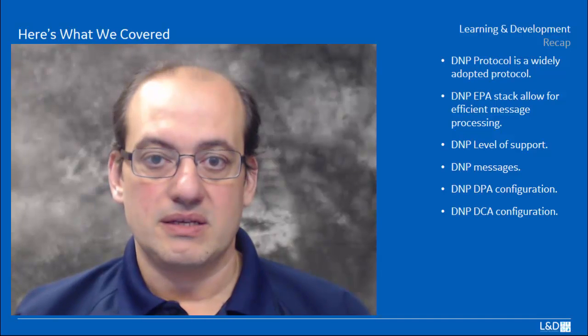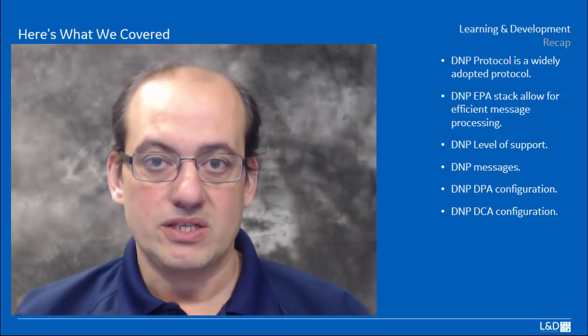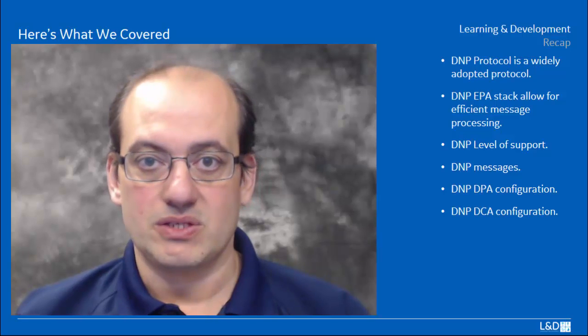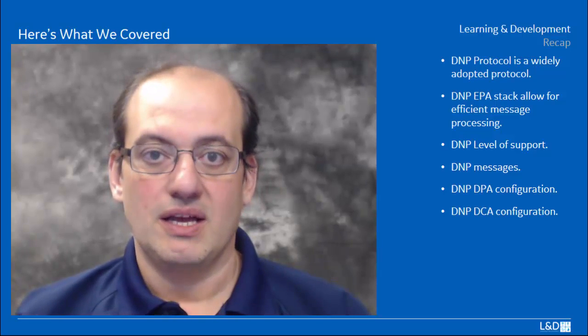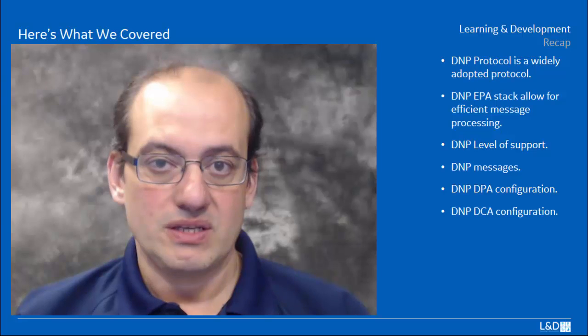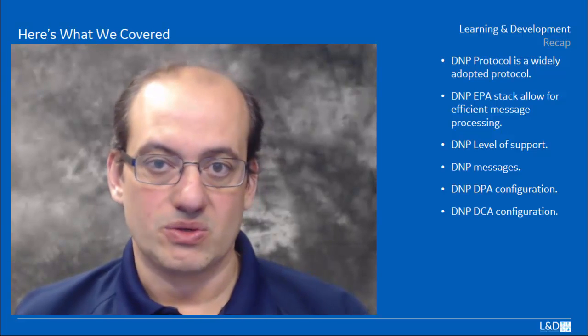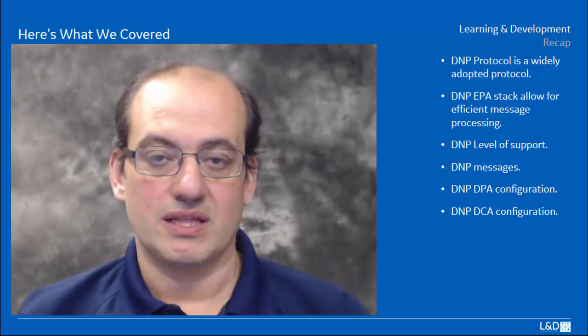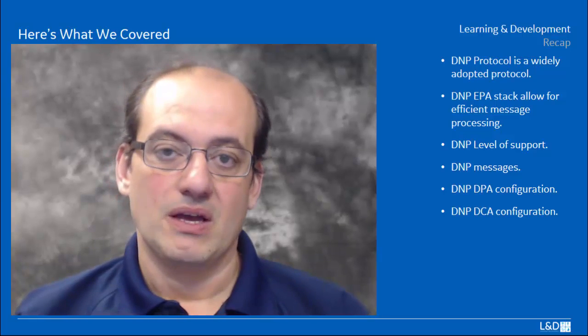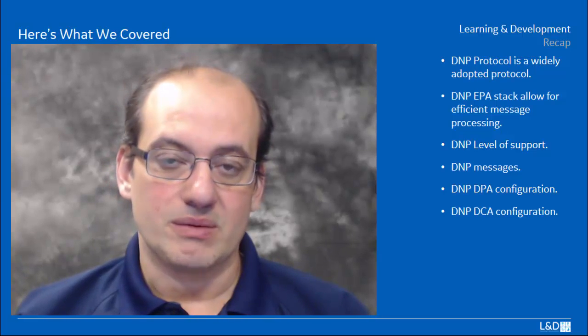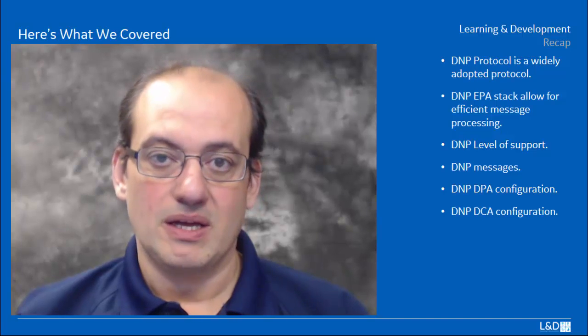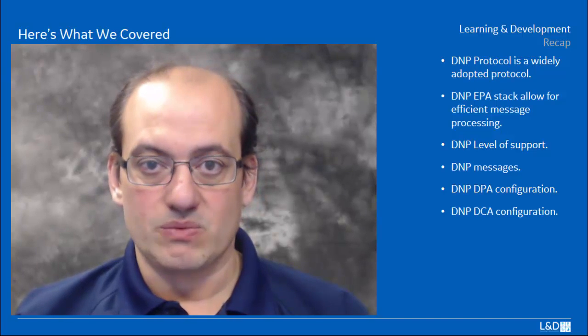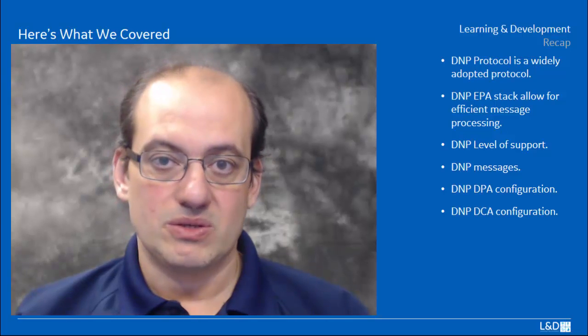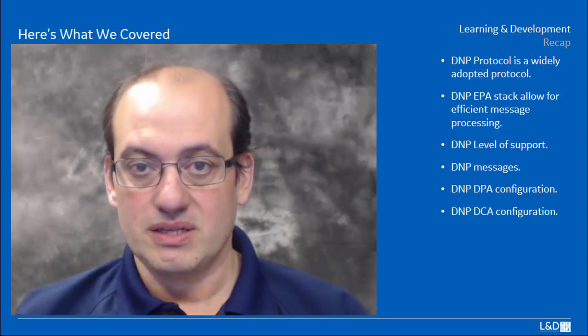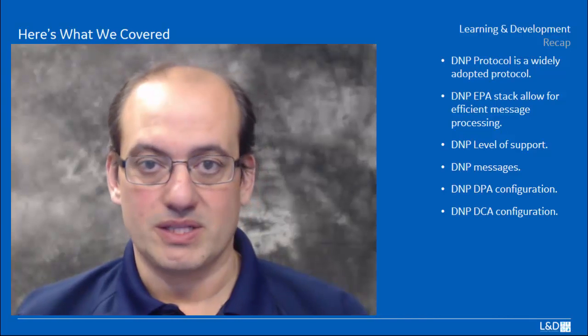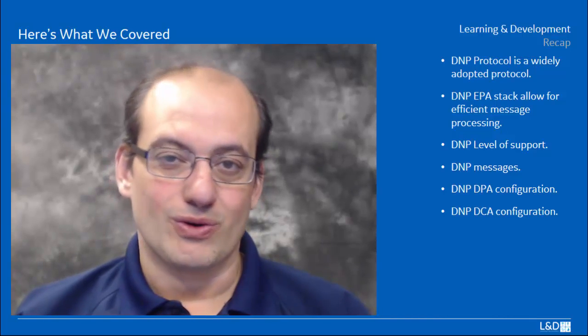For the DPA configuration, don't forget to enable the B021 application and B013, B015, which is the bridgeman between the B021 and the physical layer, which is B013. For the DCA configuration, you want to enable the B023 application. And again, you want to enable the bridgeman, which acts as a bridge between B023 and B013 in the case of a serial communication.